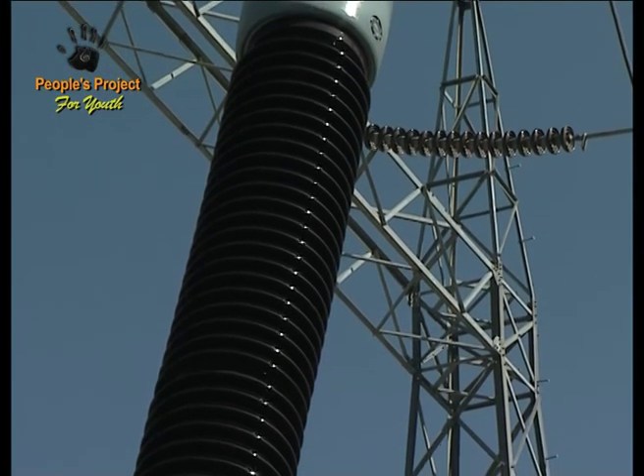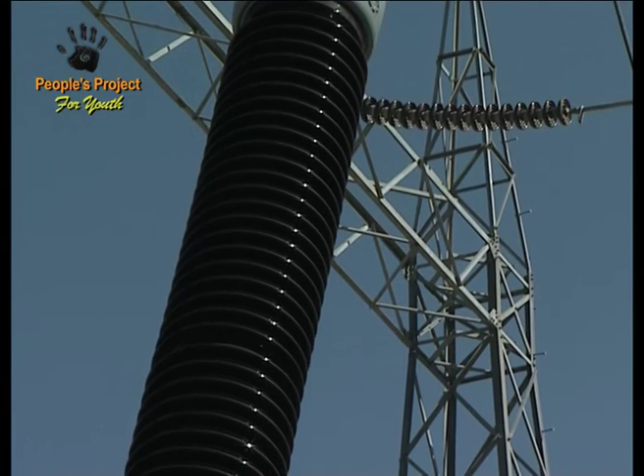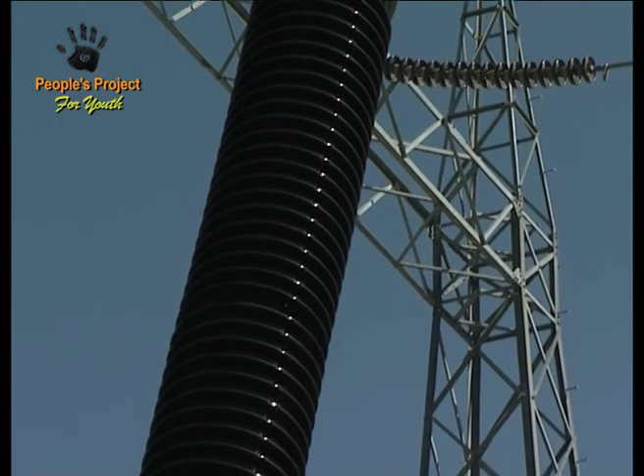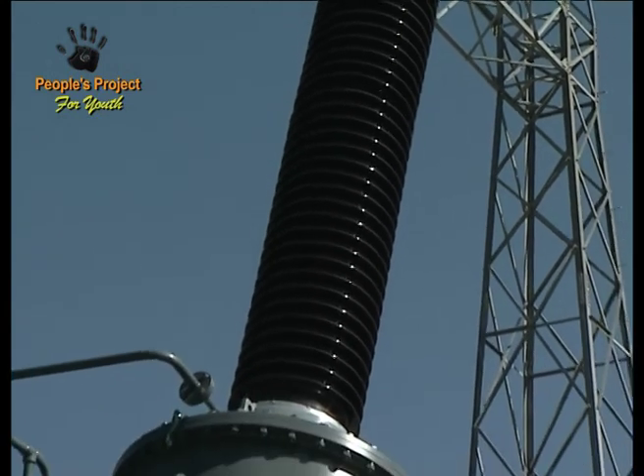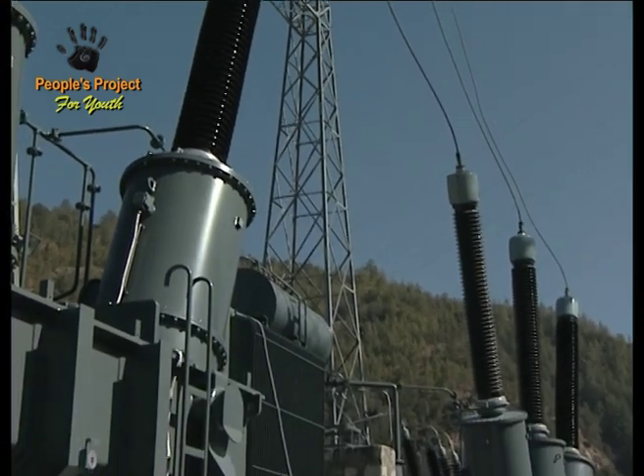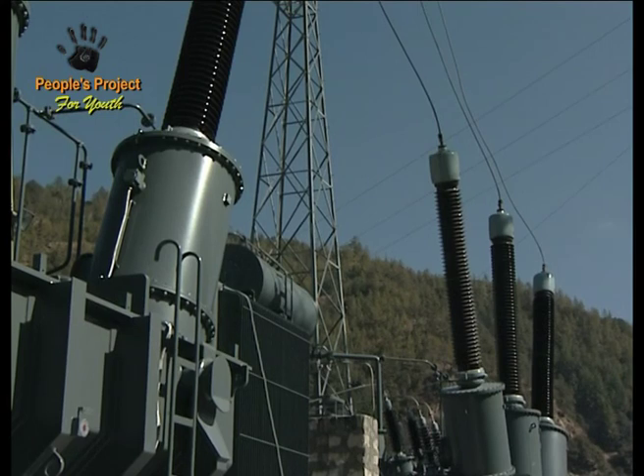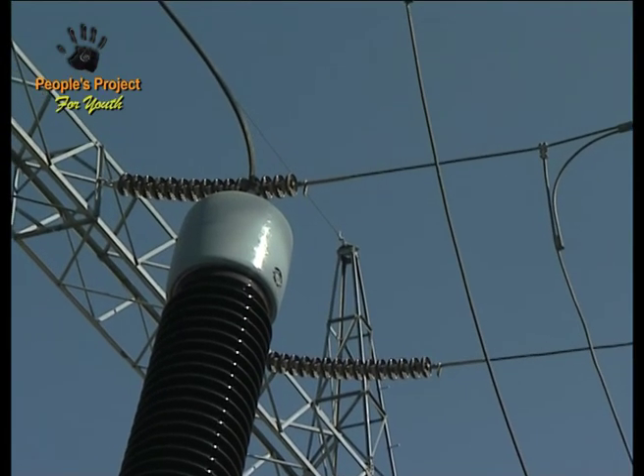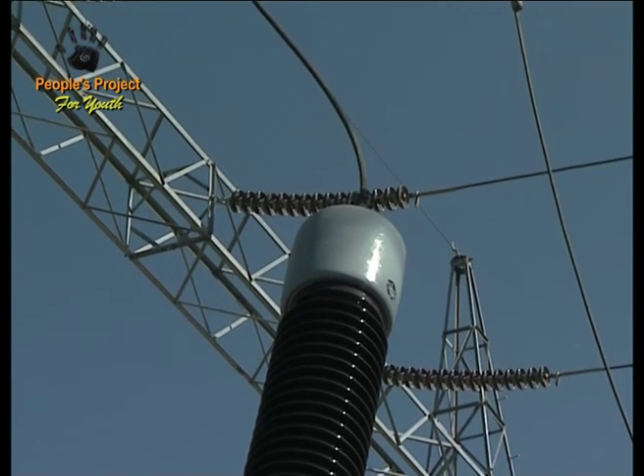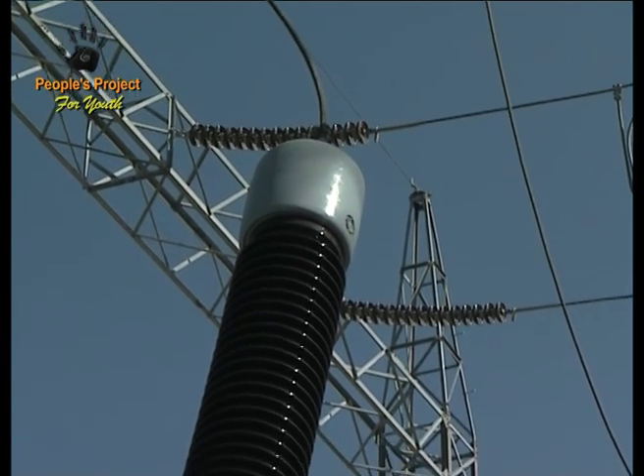The other thing you notice on these things are great big brown things, a bit like large brown caterpillars. We've got voltage coming in here at 220,000 volts, so it needs a lot of insulation. These brown things are insulation to hold up the wire. If they were made of metal, then the whole of this device down here would be at 220,000 volts and we'd all be dead with an electric spark. These brown things, which are made of pottery — made of clay — insulate the wire from the outside metal of this transformer. So these are great big brown insulators.